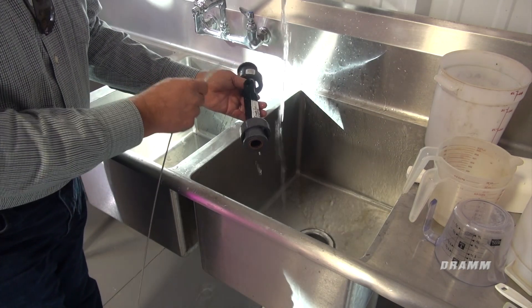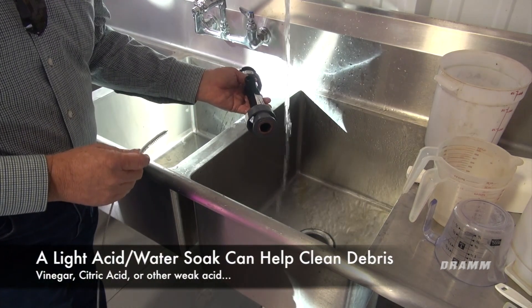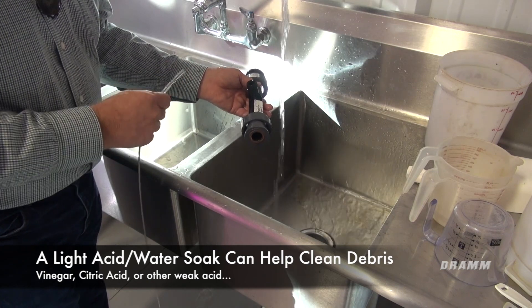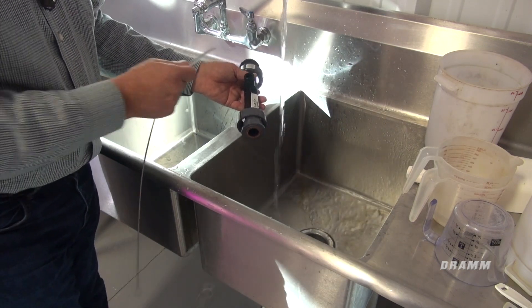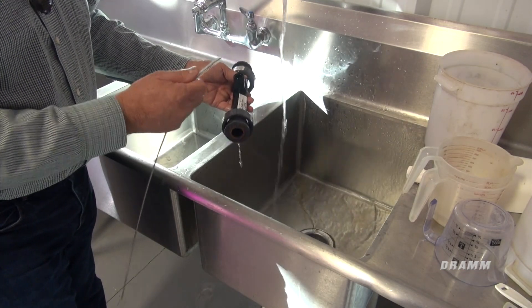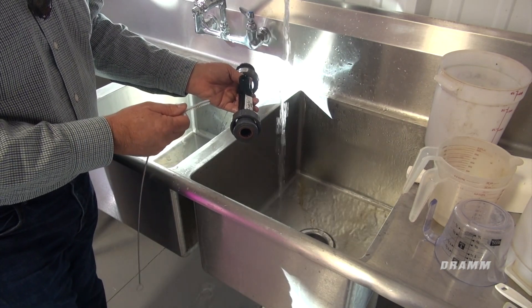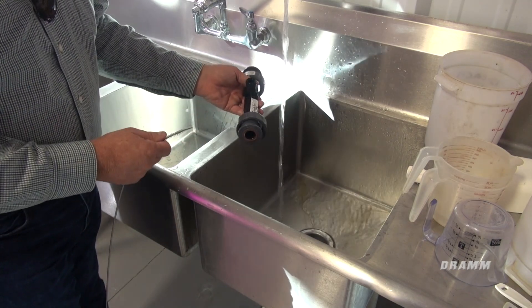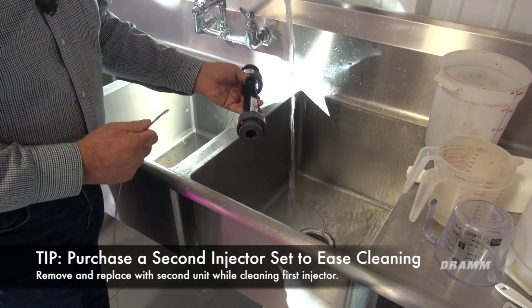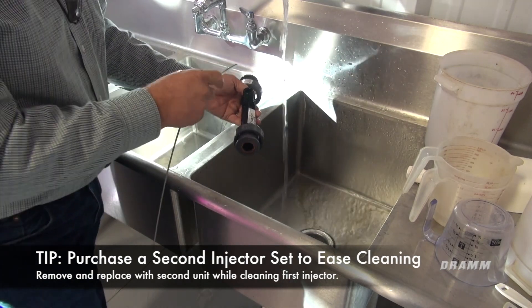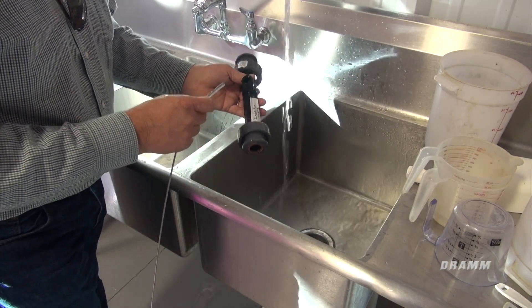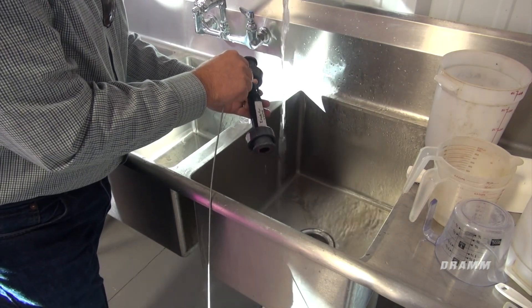But if there are more than this, we would want to put this in a soaking solution with about 10% acid and let it soak overnight. And sometimes it's a good idea to have two of these on hand. You can remove one and put it in the bucket of acid solution and let it soak overnight while you reinstall the other one. If you need to clean your injector more frequently, that's a good idea to do that, and we can easily supply you with an injector. They're a little pricey, but it's not too much to be a real budget buster.